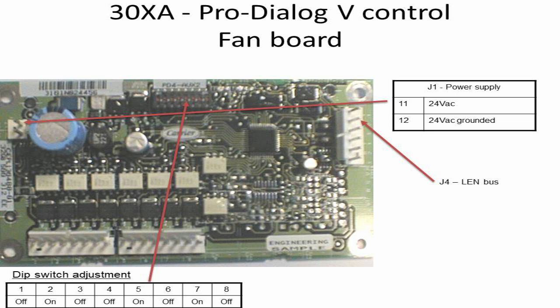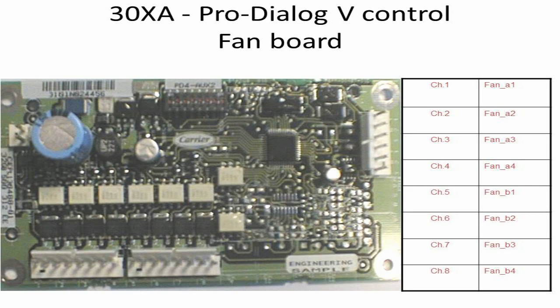Physical connections are shown on the fan board. At port J1, power is supplied to the fan board — 24 volt AC. Port J4 is used for communication to the other boards, and the fan board DIP switches are used to set the address of the fan board, as multiple fan boards are connected to the base board. At the lower right corner of the board, fan contactor control points are shown.